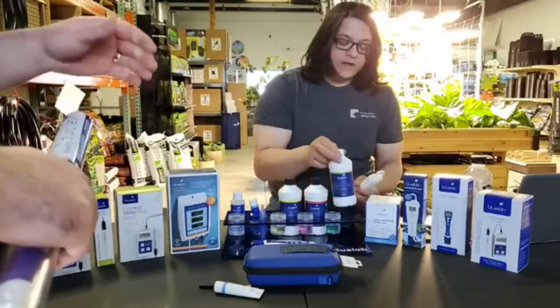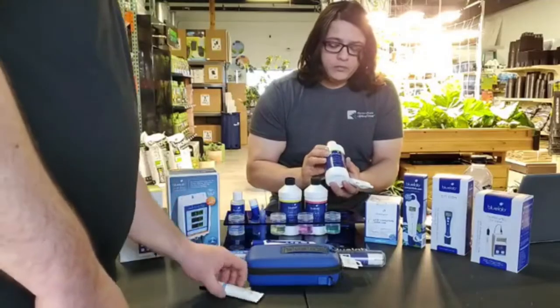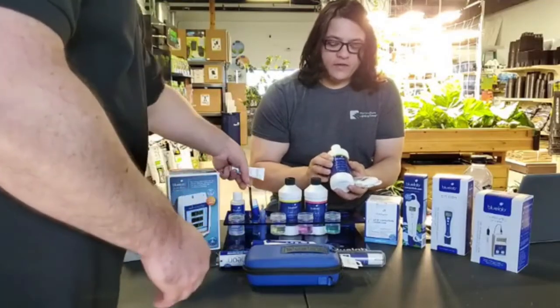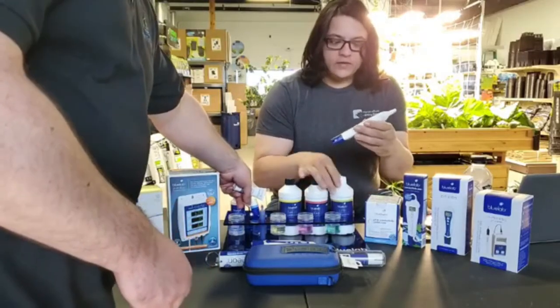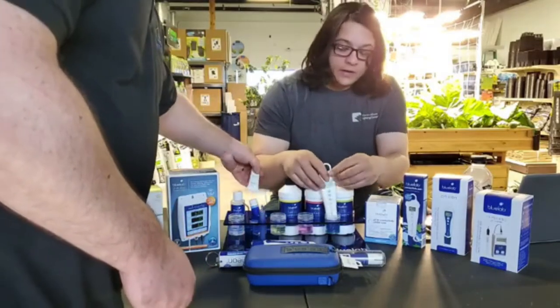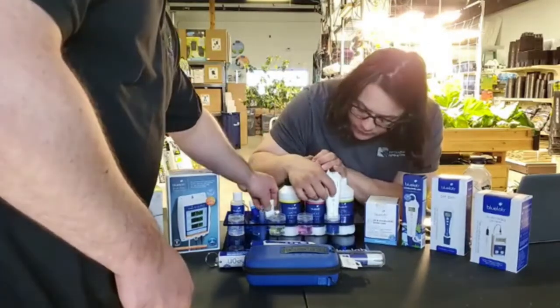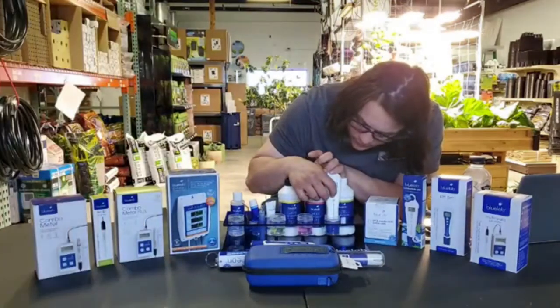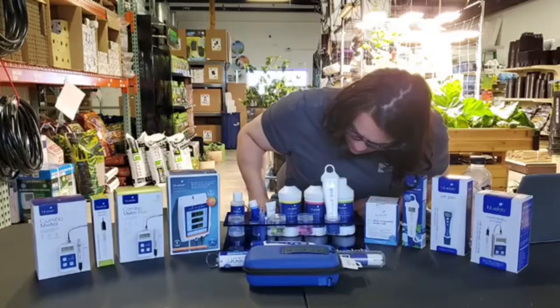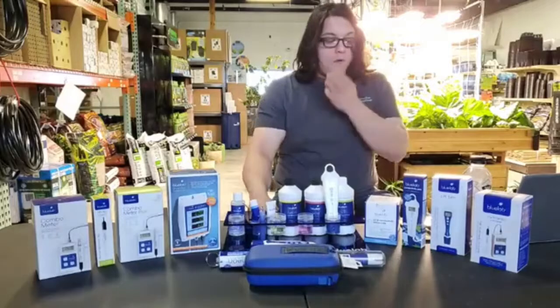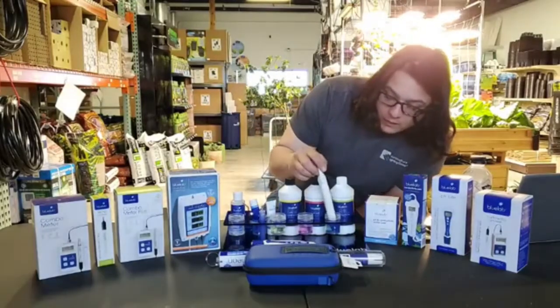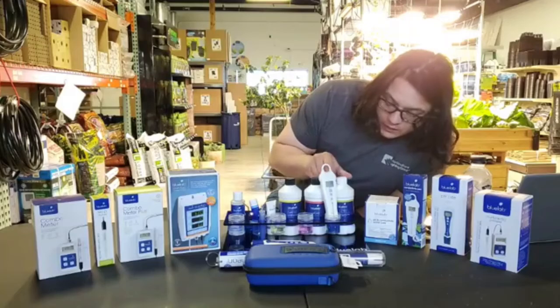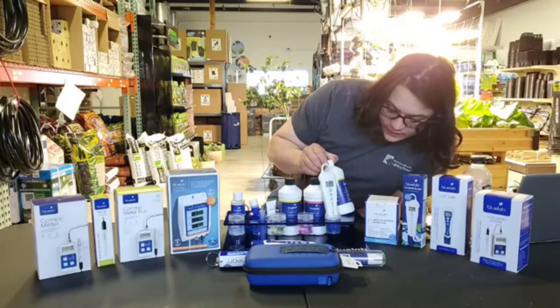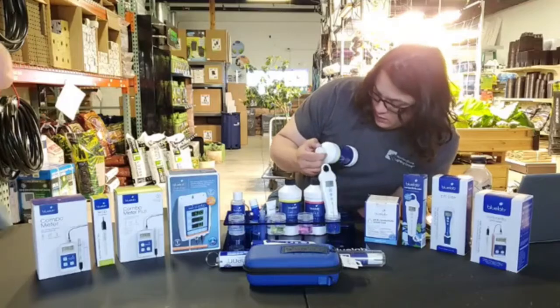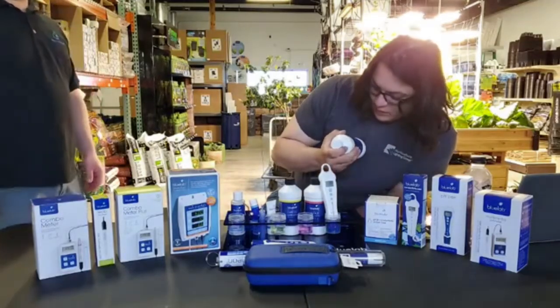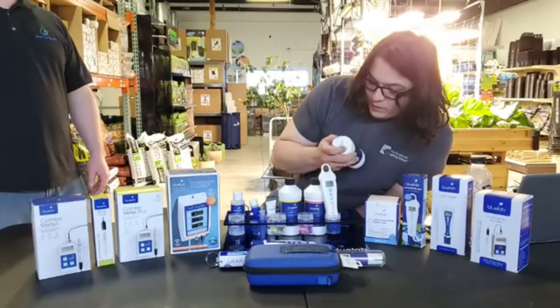So, once again, it's always super simple with these. We're looking at a 2.77 EC standard conductivity to calibrate. So we're going to stick it right in there. We're going to hold the calibration button down for about 3 seconds. Should say calibrate. Yep, there it goes. Okay, so for EC for this, we are looking at 1385 ppm on a 500 scale, or 1940 ppm on a 700 scale.